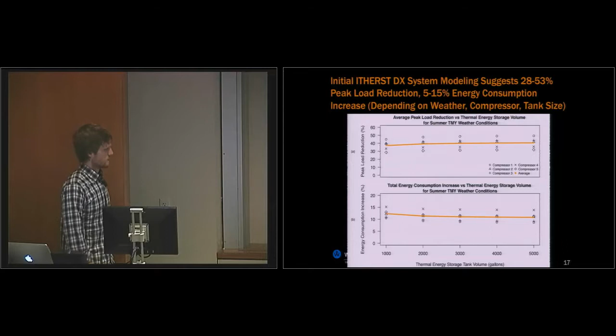So the performance of the system is impacted by both weather, compressor, and tank size, but the biggest factor is compressor. So compressors operate differently. They have different styles of compressors. What this suggests is that you need to pay attention if you were going to design a system around this, that you find a compressor that operates very efficiently at low delta T or low condensing to evaporating temperature differential, those low pressures. Weather also has an impact.